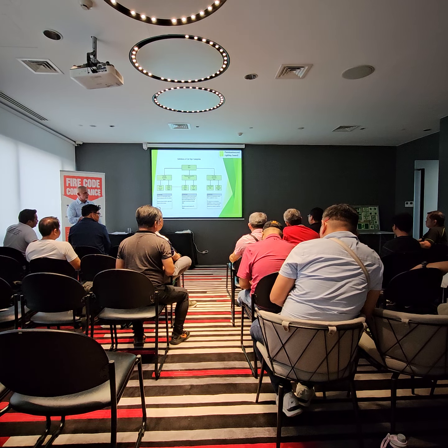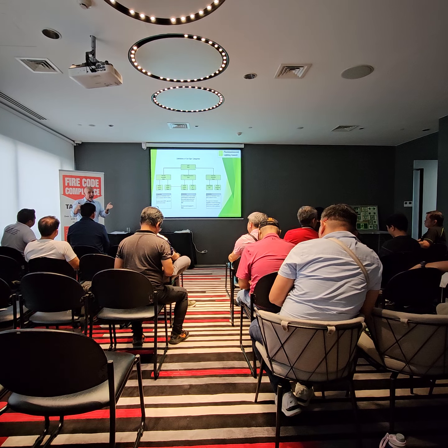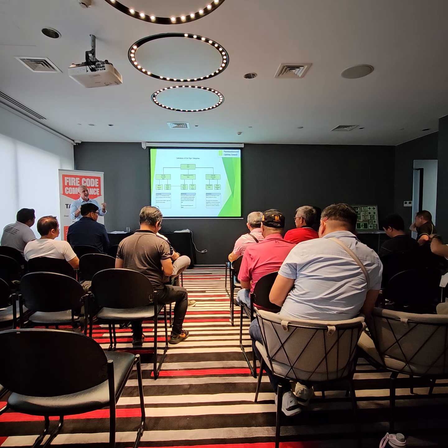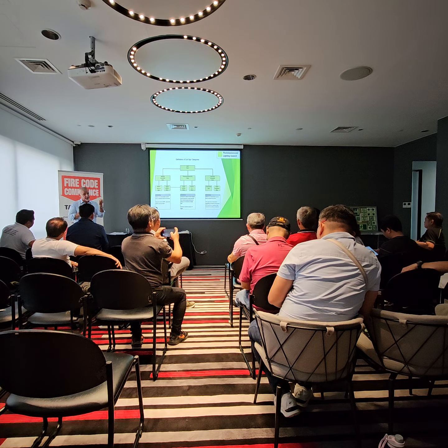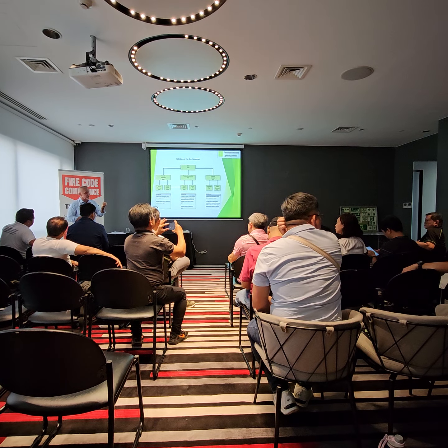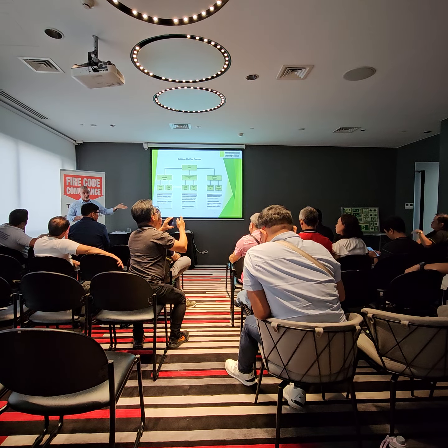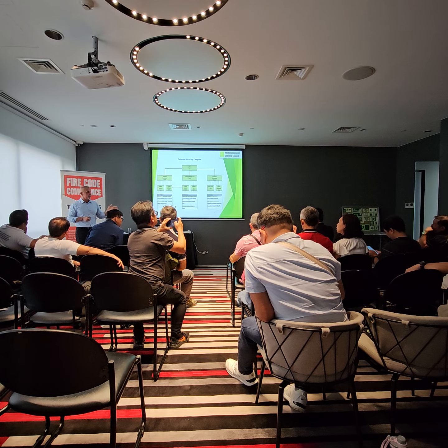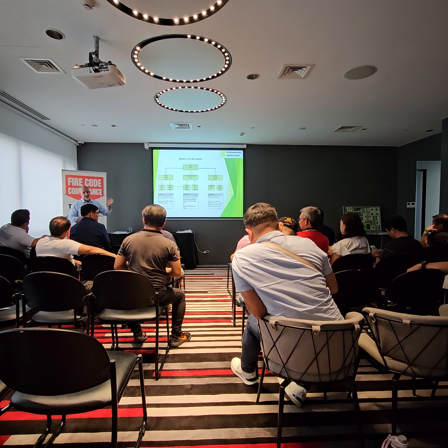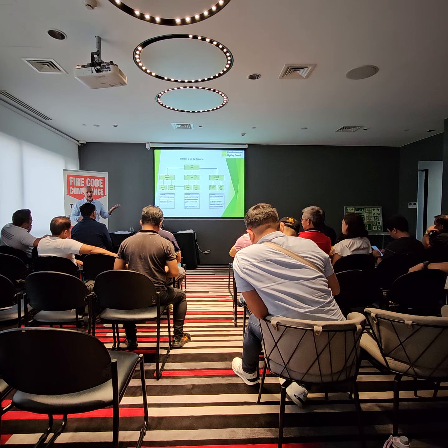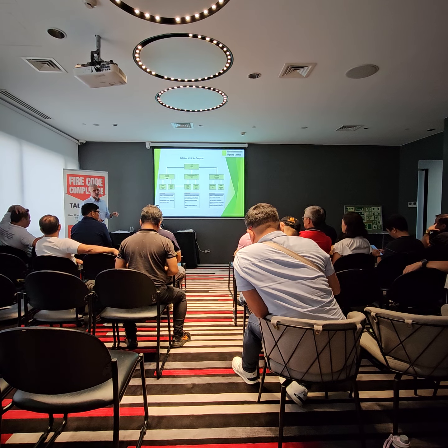And the interesting thing about these is that you're able to reduce the number of parts in the device. So clearly there's no battery charging electronics. That's one of the things that fails most in these signs. So you take all those bits out and they just last a lot longer. The LEDs, in some test scenarios, have been tested in a practical sense and are running for over 30 years without failure. So it's quite a step up.